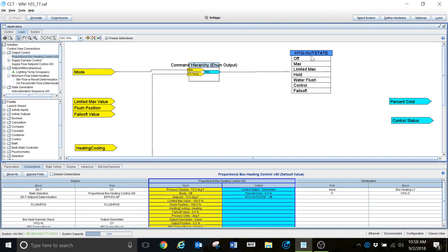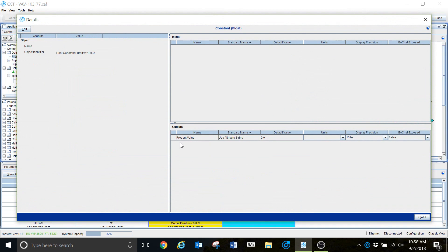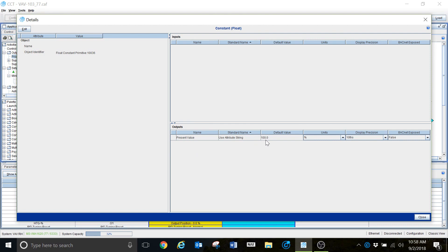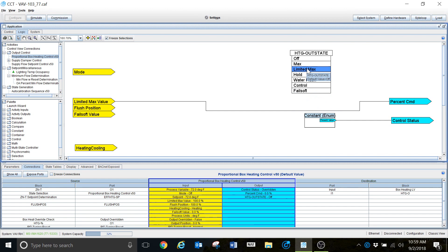Heating out state — this section here is basically the mode section. When you click on one of these states, you're going to notice something change. When I highlight this, you can see that this is the Off state. This is basically going to control the percent command, the control status, that sort of stuff. This is a state-based logic block. If I double-click into here, you can see that the default value for this is zero — that means when the box is unoccupied, it's just going to close that valve. When I select the next section under Max, you can see it changing as well. The present value here is 100 — so when this box is in maximum heating, it's going to command that valve to 100%. Then there's Limited Max, Hold, and all of these are basically the different states of this particular logic block.